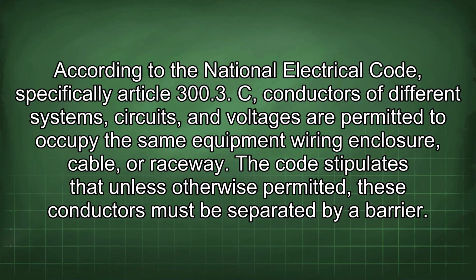According to the National Electrical Code, specifically Article 300.3(C), conductors of different systems, circuits, and voltages are permitted to occupy the same equipment wiring enclosure, cable, or raceway. The code stipulates that unless otherwise permitted, these conductors must be separated by a barrier.